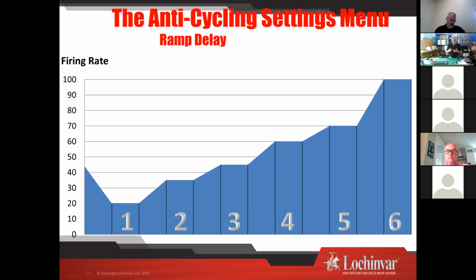We're going to be able to run clean. That's the big part, is your boiler burns clean. It doesn't cycle on and off. Side benefit of that is things like if you slug, so back when we all had cast iron boilers sitting down in our basement, they were hot, and you turned a zone on that might have been off for a while, and you slugged 180-degree water into it, you got that tick, tick, tick, tick, tick, tick of the baseboard, and you got all the noise and everything else.